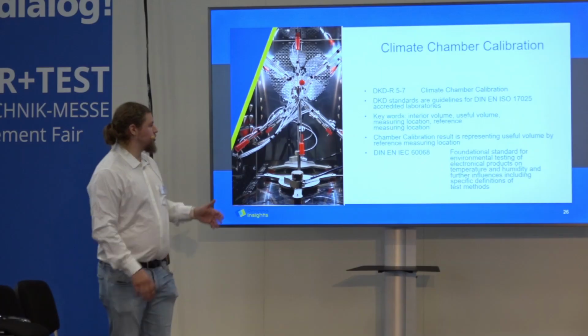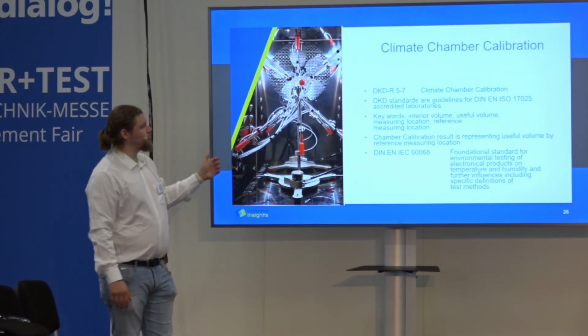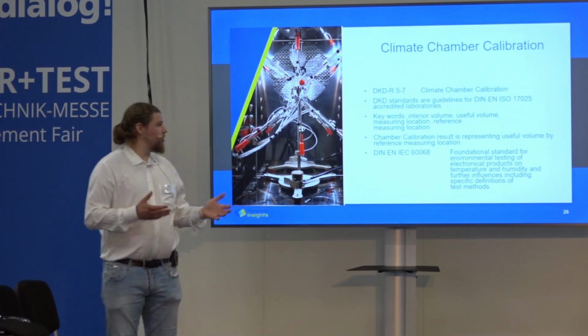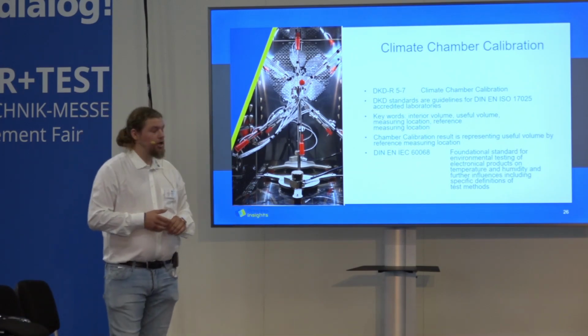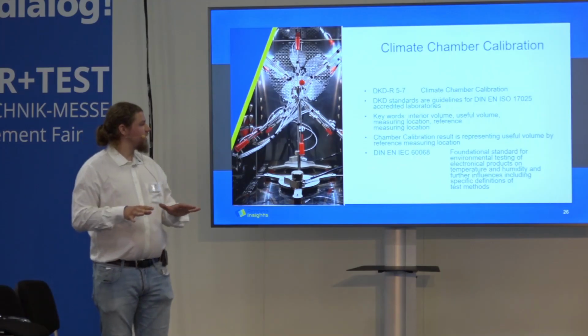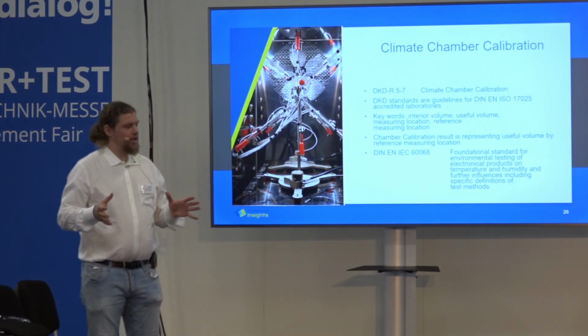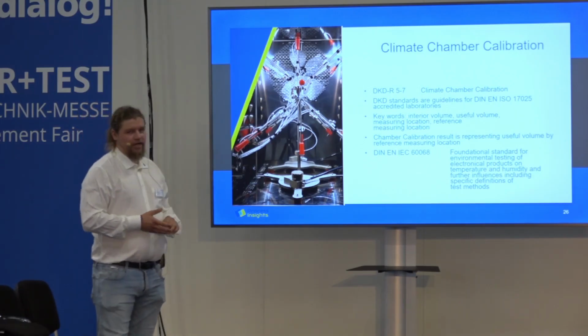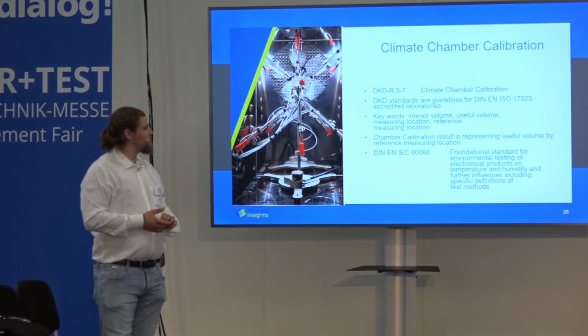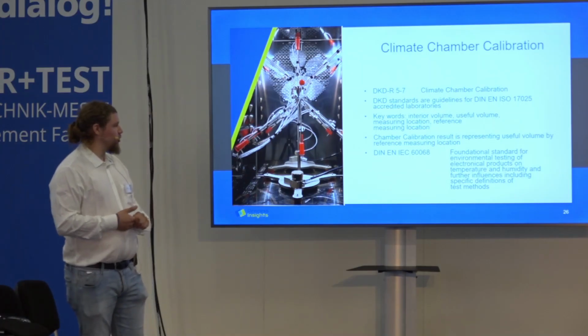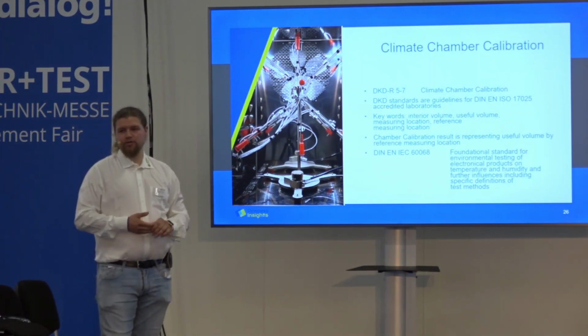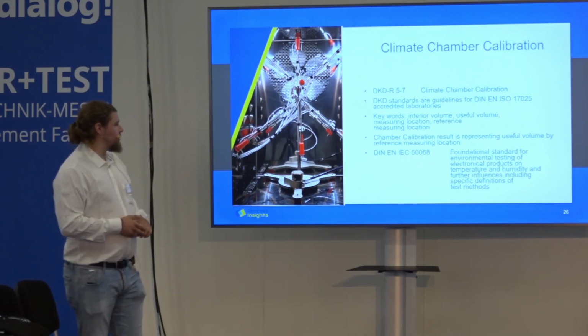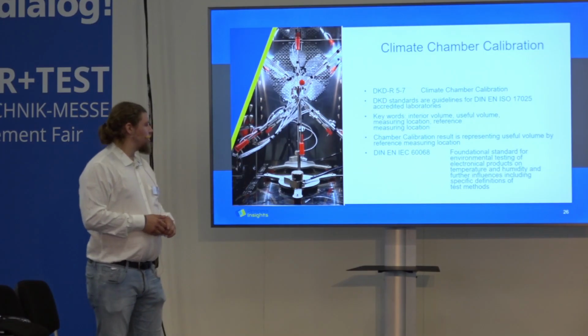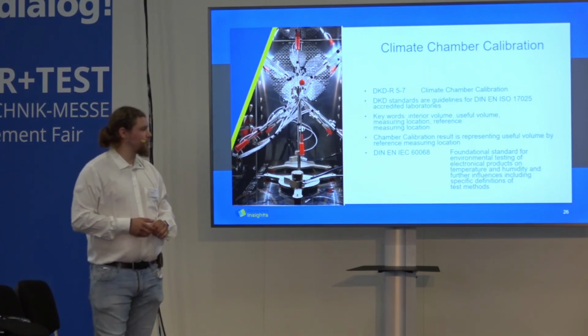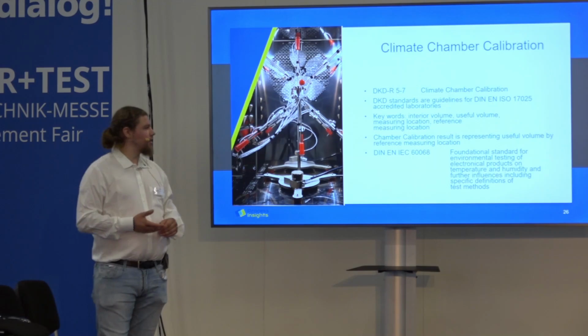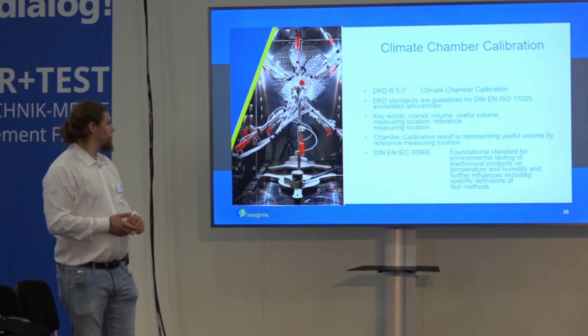Talking about climate chamber calibrations, it's useful for orientation to know the keywords: interior volume, useful volume, measuring location, and reference measuring location. You need to orient, and you have to define the chamber and the locations to be able to give a representative value. If the chamber calibration is set up correctly, then you have a representative measurement for the chamber.